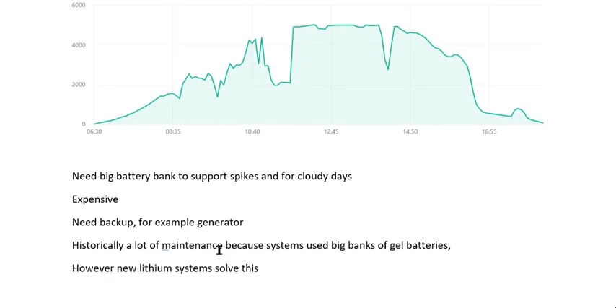Historically, off-grid systems have had a lot of maintenance because they had subpar battery management and big banks of gel batteries that need a lot of maintenance - you have to control temperatures, check things, and it's dangerous if you don't. Compared to newer lithium batteries, gel batteries are a lot more dangerous and have to be maintained and monitored much more.